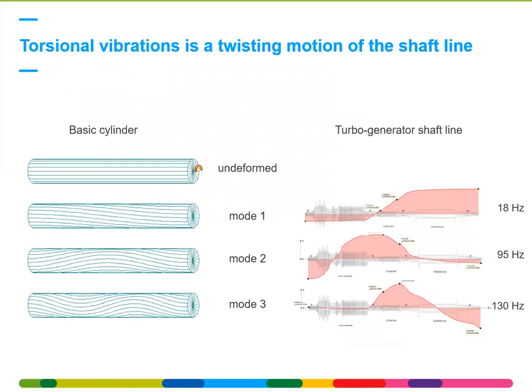So some important characteristics first, the basics of torsional vibrations, to get everyone on the same line. On the left, you see a basic cylinder, which in torsional vibrations has different natural eigenfrequencies. For this simple cylinder, you can see the first three modes. The first one is the simplest, where you have a twisting motion of both ends in anti-phase against each other. The higher you go in frequency, mode 2, mode 3, the more complex the deformation gets. Torsional vibration is actually a twisting motion of the shaft superimposed on the steady state rotation.